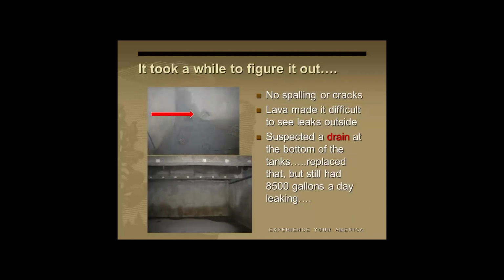When we started thinking about where they could leak, we figured it must be the drains out of the bottom of the tank, since there are some short sections of pipe associated with those drains that we hadn't replaced along with the rest, just because they were hard to get to and we didn't think it was necessary since they were just drains. But since we thought we were leaking about 8,500 gallons a day out of one of the tanks, especially the 100,000 gallon one, we knew we were leaking it somewhere, and we suspected the drains. So we put together a project and replaced the drains.